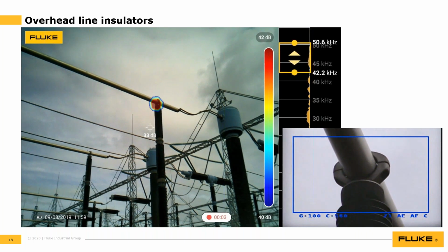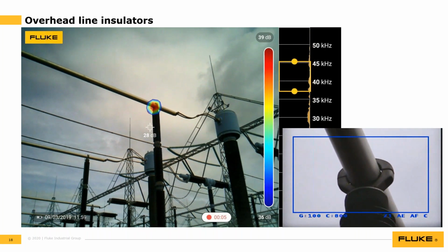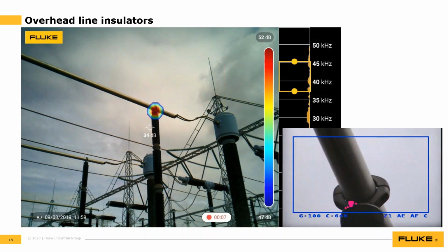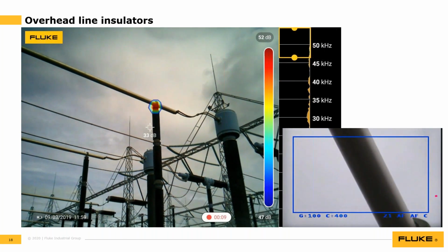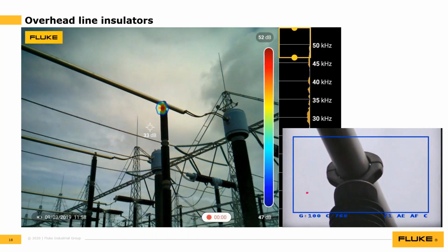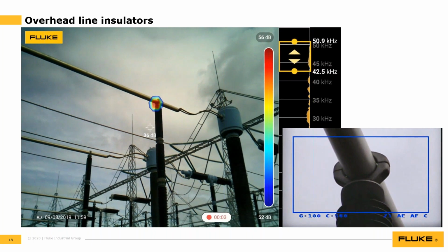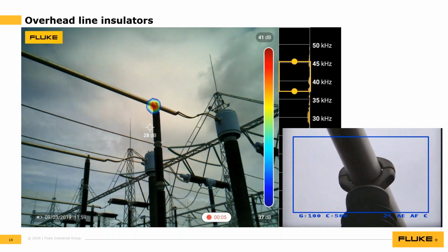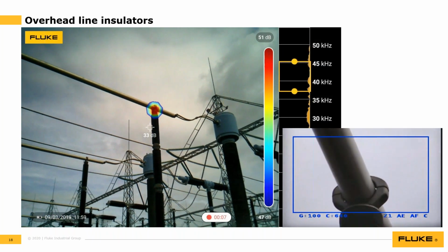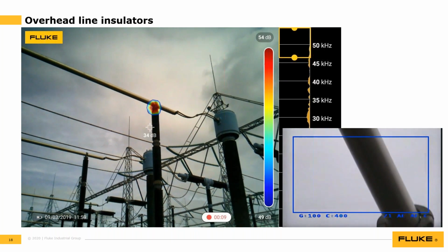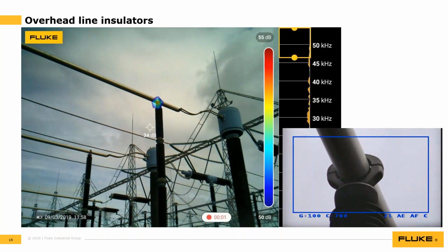What you need is line of sound, as I'm calling it - you don't have to have direct line of sight. That partial discharge might be on the back side of that insulator, but the sound is emanating and coming toward us. So there's another slight advantage, a real benefit there.